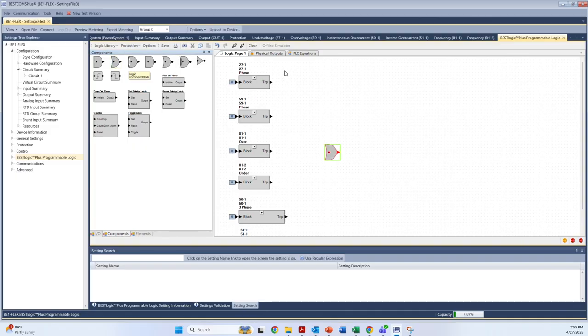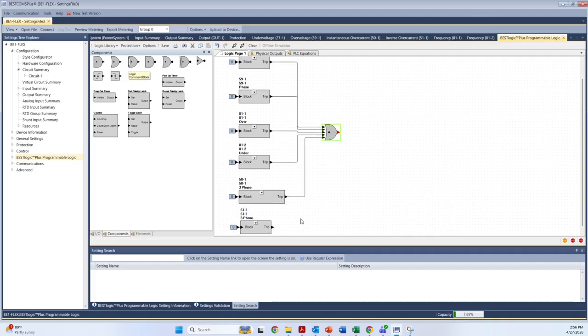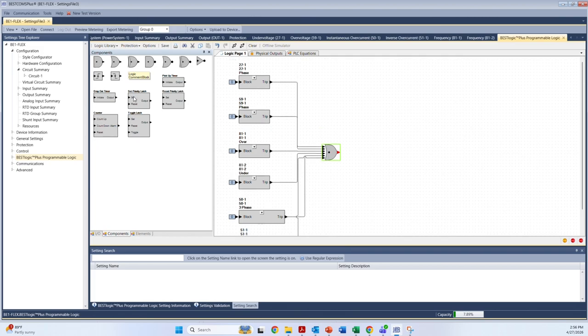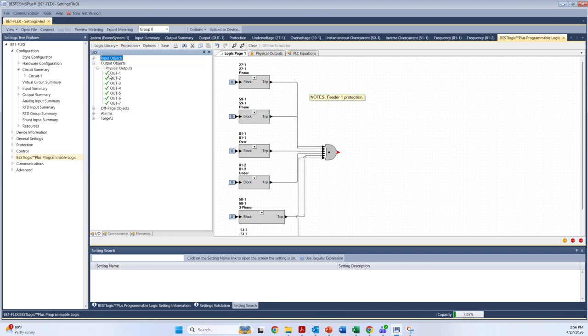So now I'll use an OR gate and connect all of them to the OR gate. So any one of these will trip the breaker. You can leave notes, so you can leave any notes for the technician or operators. And I will select the trip output. Connect that. Notice everything goes to green down there with the LEDs. Save the file.